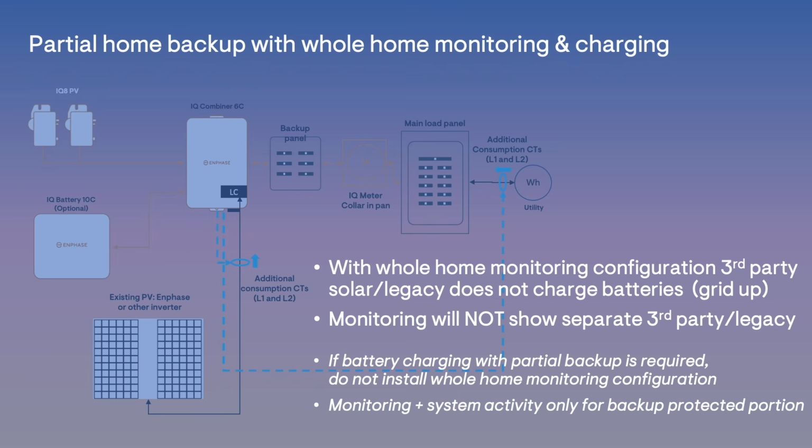If your partial home backup scenario requires that the older system charges the new batteries, do not install whole home monitoring. Rather, monitor and configure only the backup protected portion of the site. In either configuration, the pre-existing system does charge batteries during a grid outage.